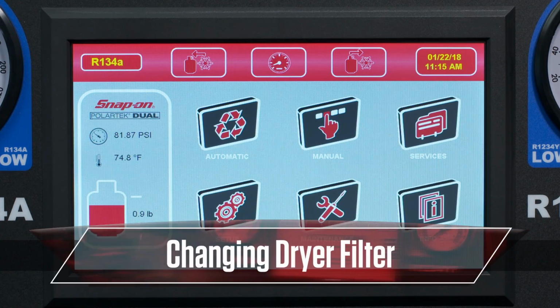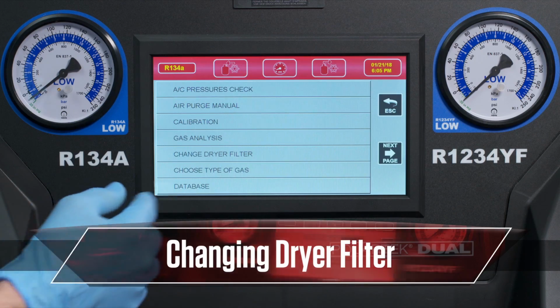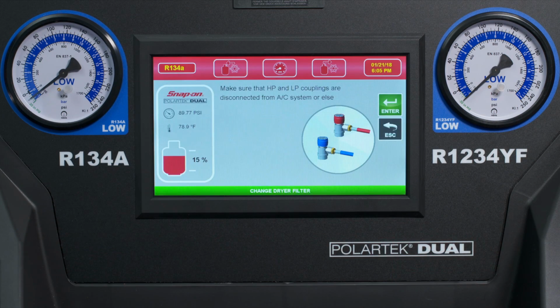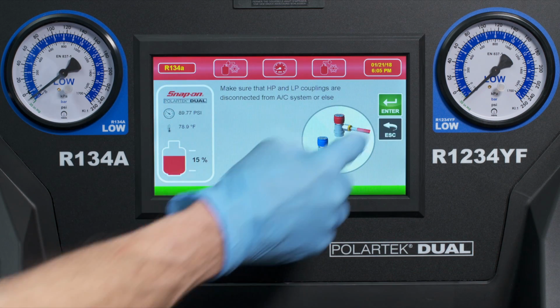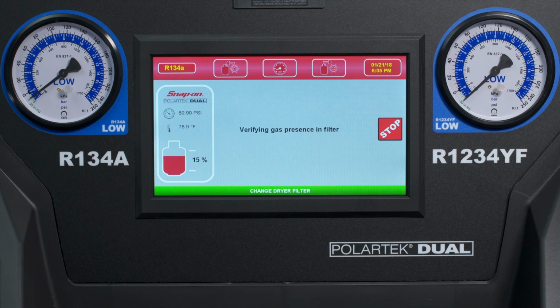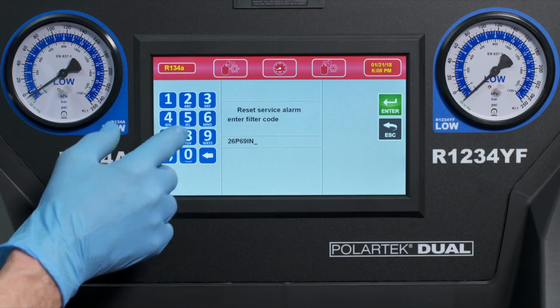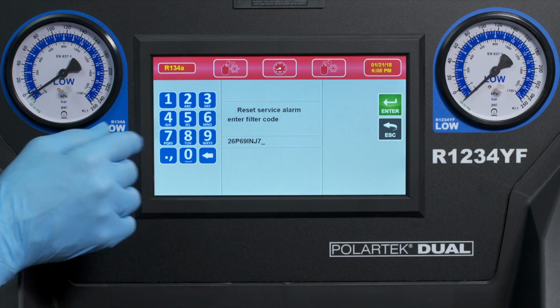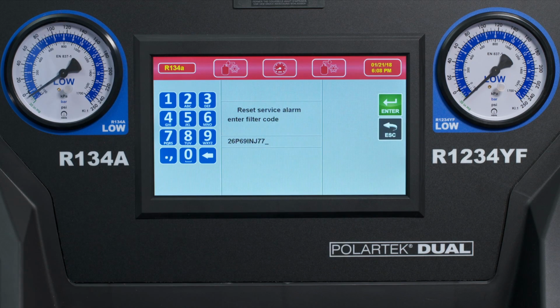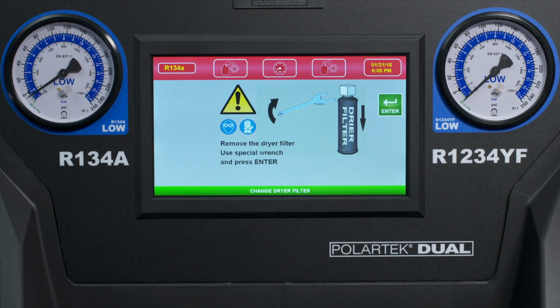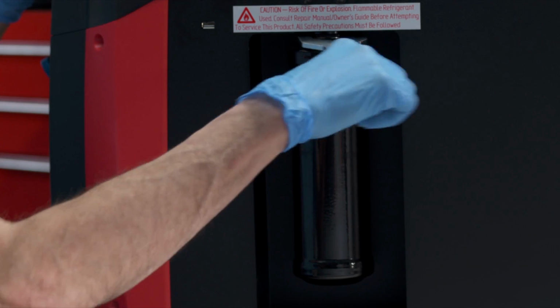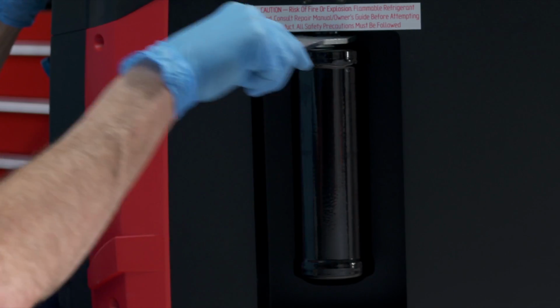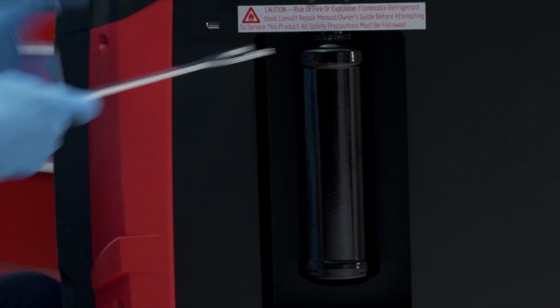From the main screen, select Maintenance, then select Change Dryer Filter. Verify that the hoses are disconnected from the AC system. The machine will start the verification and recovery process. The machine will then prompt you for the filter code found on the new filter. To change the filter, a special wrench is provided for removal and reattachment of the dryer filter. Remove as shown.